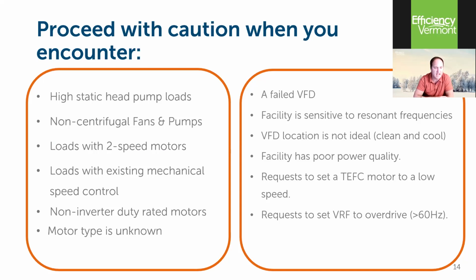Loads with existing mechanical speed controllers, non-inverter duty rated motors. This is an important one. VFDs are also referred to as inverters. In order for a VFD to work, the insulation class on the motor has to be inverter duty rated. If it's not, you risk burning up the motor. So again, this doesn't necessarily mean that's a no-go scenario. It just means that project might morph into a motor and drive project as opposed to just a drive project.